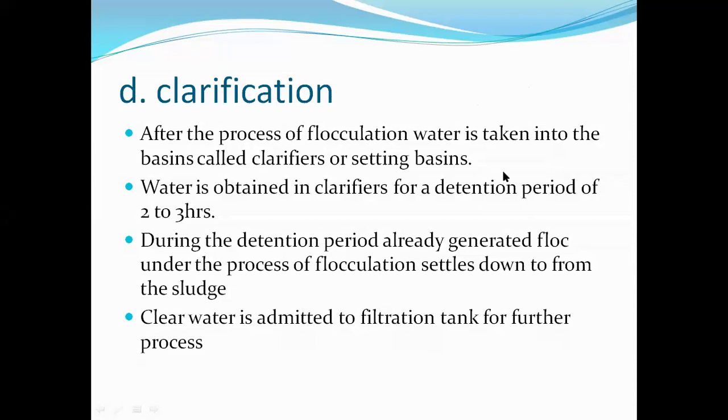In the clarification process, the water from the flocculation tank goes to the clarification tank or settling tank. Then it settles for the detention period of 2 to 3 hours. After that, the floc settles at the bottom and forms the sludge, and the clear water is admitted to the filtration tank for further processes. Hope you all get this process of clarification or sedimentation.